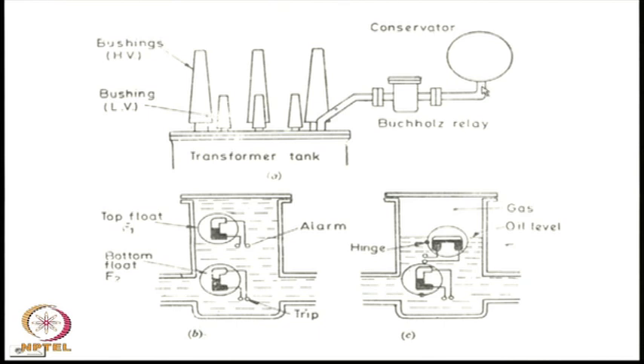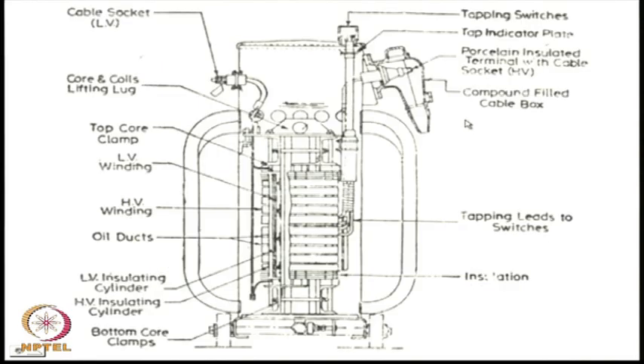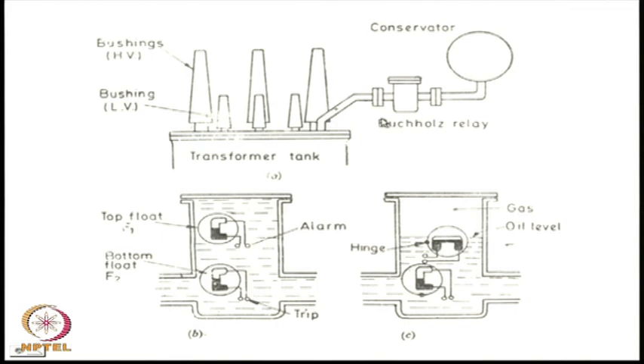The reason why it is done is so that the minimum of the transformer oil surface comes in contact with air and it does not absorb moisture from the air. The conservator provides a space for expansion of the oil. As the transformer heats up, the oil expands and flows through the tube to the conservator. Now, this conservator, although it is not shown here, is connected to the external atmosphere through what is called a breather.